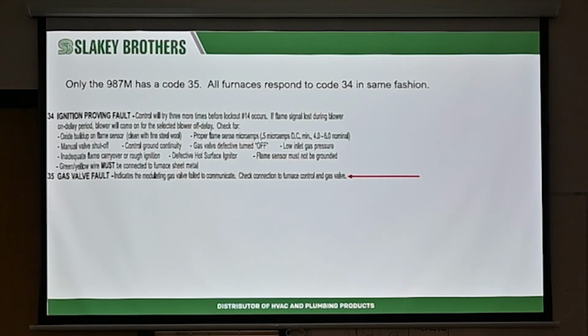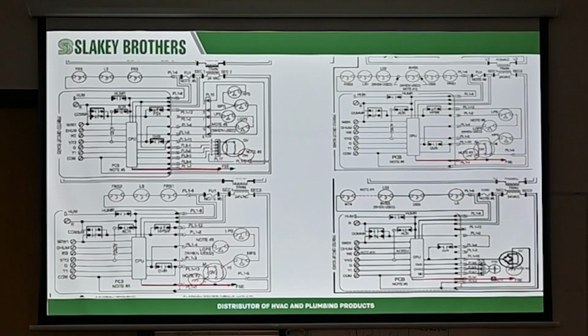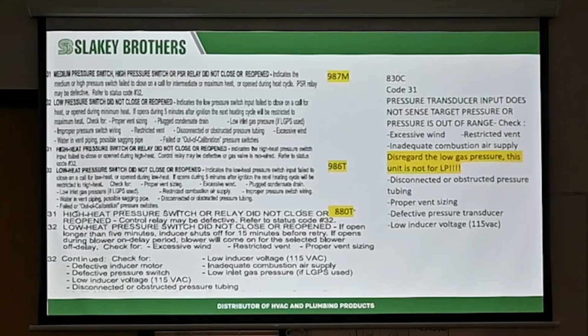Every time you change it around, upflow, downflow, upflow comes fine right out of the factory, but horizontal right, horizontal left, or downflow, you have to change the stuff, and sometimes we just put them in the wrong spot, and it just happens. So when it comes to pressure switches, especially for you guys, again, on startup, usually something's just disconnected. It's just in the wrong spot. On a rare occasion, it's a faulty switch from the factory. But again, that's where a manometer comes into play. You confirm you've got the right pressure. You confirm that the switch is not closing, and you're good to go.